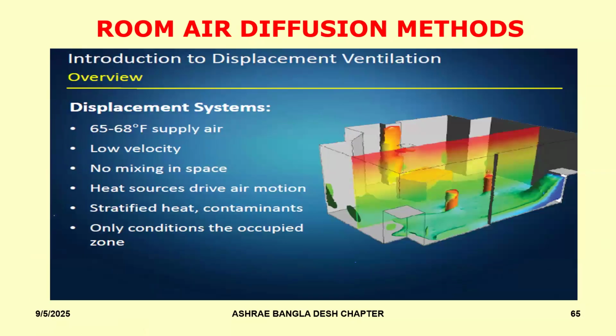But in displacement, we do exactly the opposite. What we do is we supply the air directly into the occupied space, which means the supply outlets are placed in the room at the floor level so that the air comes directly into the occupied space. Since the air is coming directly into the occupied space, we want to make sure that the temperature of the air is as close to the room temperature as possible. So if we are maintaining the room at about 75, then my supply temperature would be around 68 to 70 degrees Fahrenheit. Since the air is again coming directly into the occupied space and we do not want drafts, typically we said that for people to feel comfortable at about 75 degrees Fahrenheit, the air velocity should not be more than 50 feet per minute in the cooling mode.